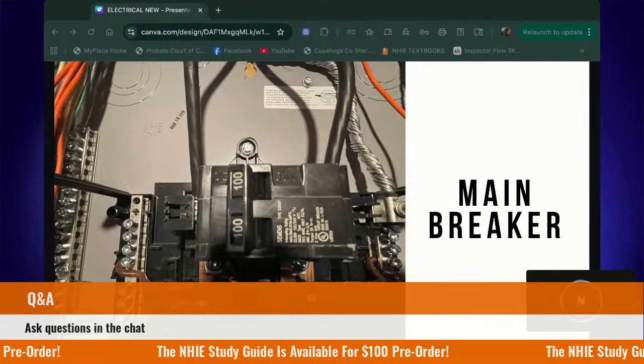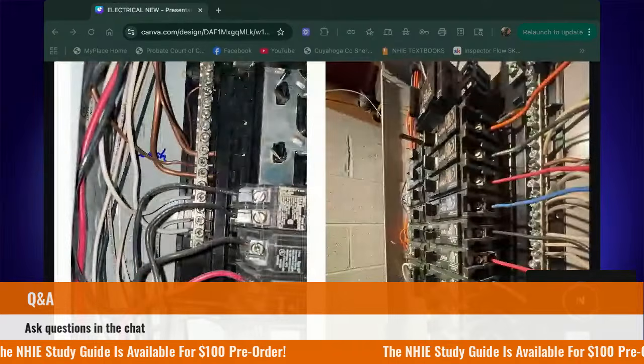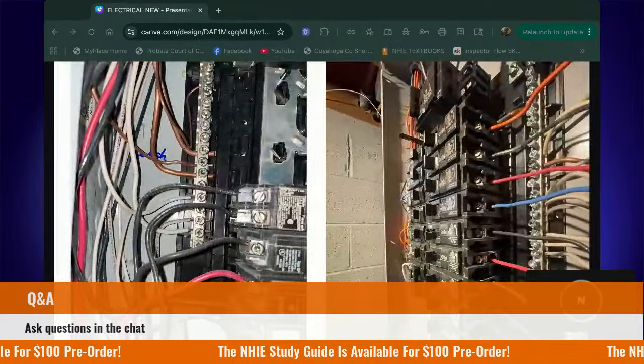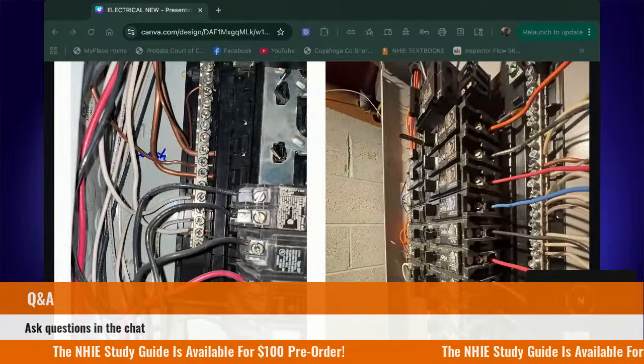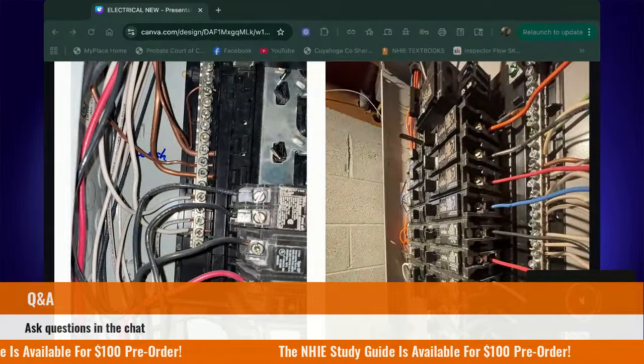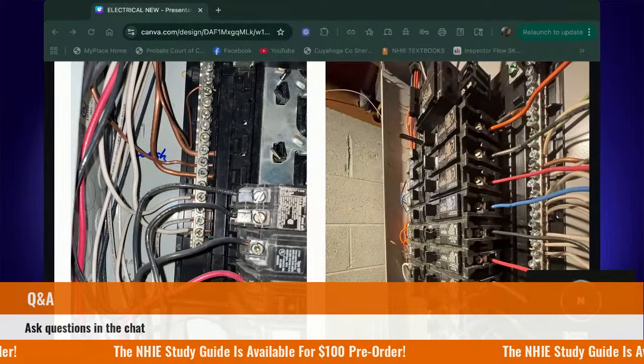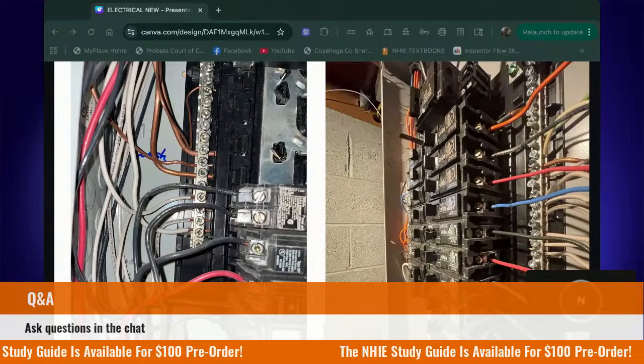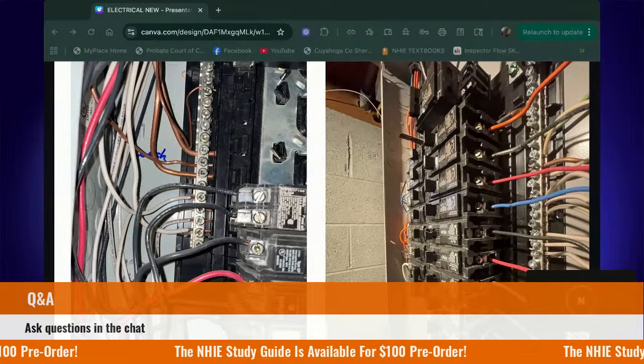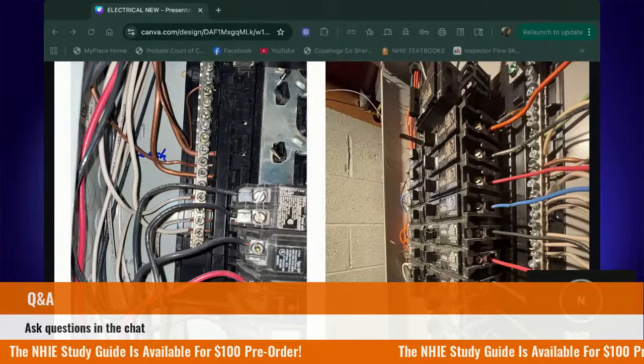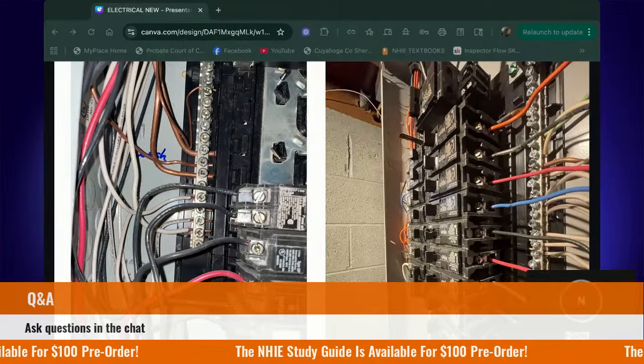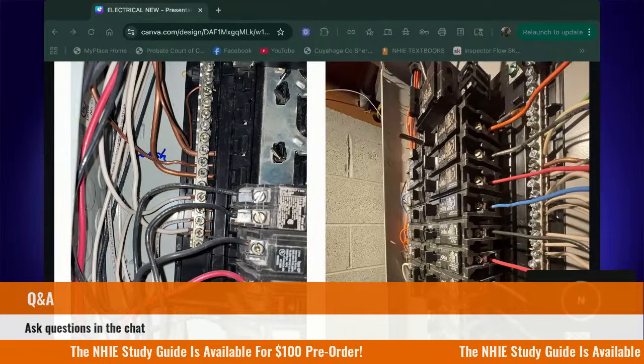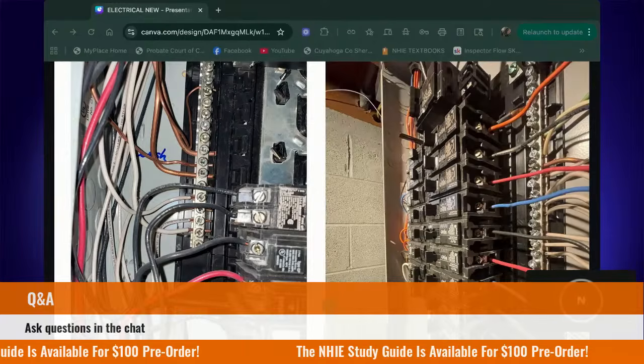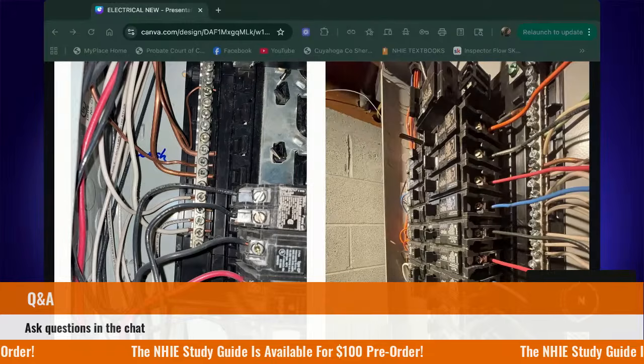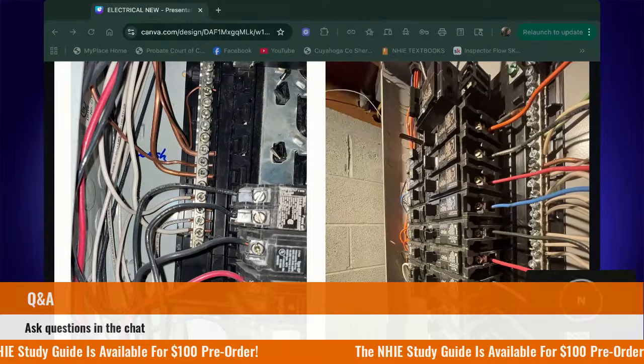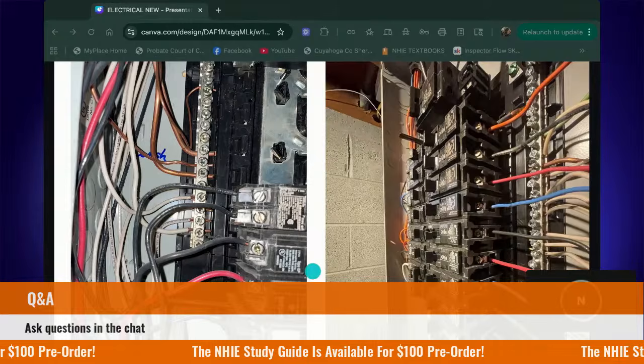All right, so next we have our bus bars. These are the metal strips that are in your panel, and they basically help distribute the electricity throughout the entire system. So you have a couple different bus bars. Okay, you've got to think of a bus bar like a highway. The bus bars are the main highway carrying electricity through the panel, and then you have your circuit breakers here, which are like off ramps, right? You could take power off of the highway and send it to a certain room.